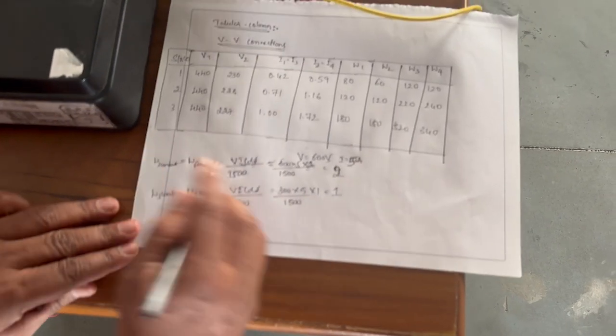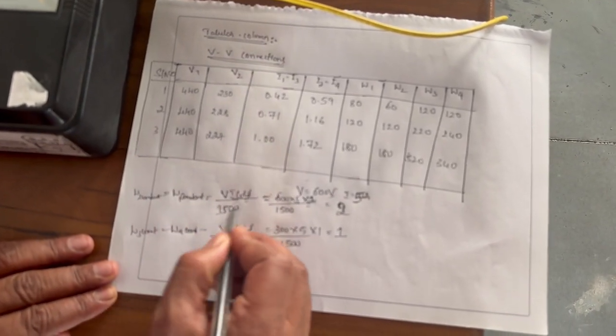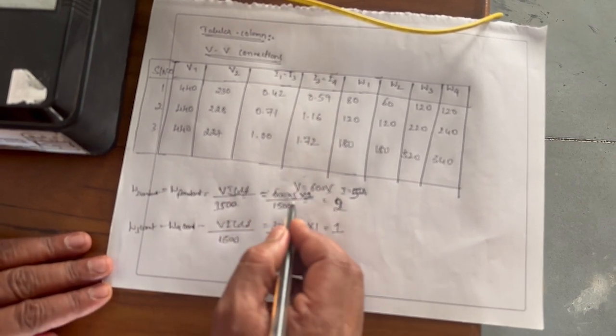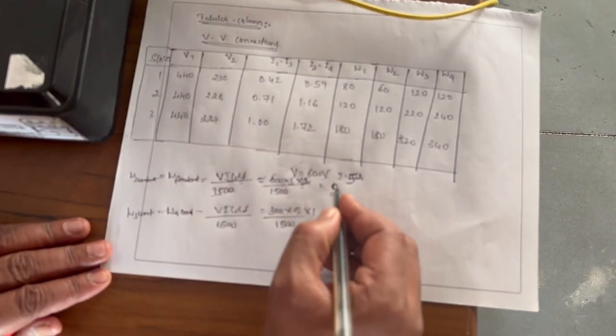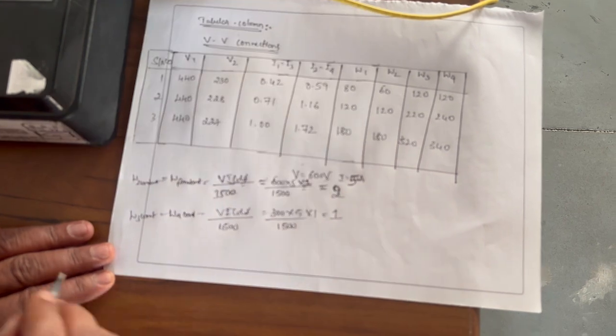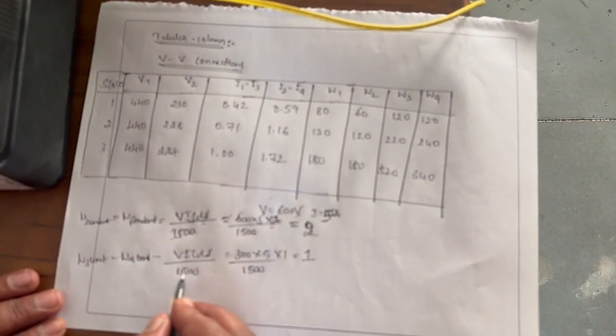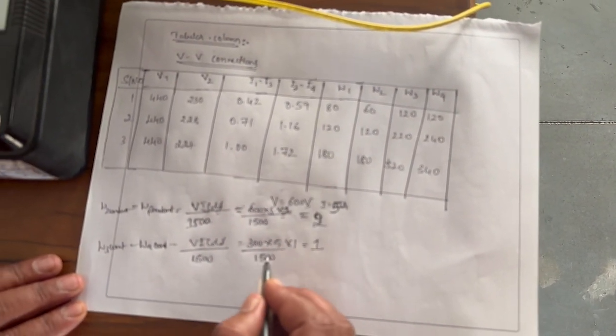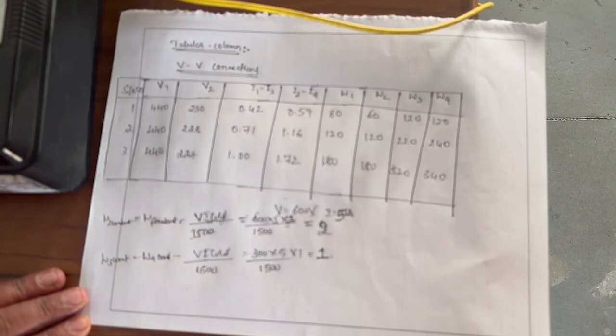This is the multiplication factor: W constant is equal to VI cos phi divided by 1500. That is 600 into 5 into 1 divided by 1500. The W constant will be 2. Next, for W3 and W4, VI cos phi divided by 1500, that is 300 into 5 into 1 divided by 1500. So the W constant for W3 and W4 will be 1.